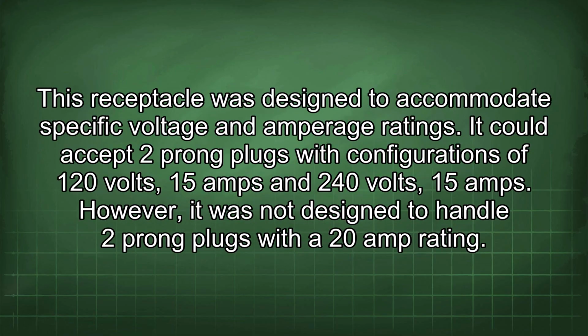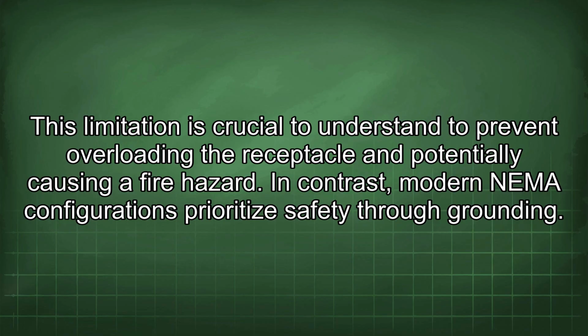This receptacle was designed to accommodate specific voltage and amperage ratings. It could accept two-prong plugs with configurations of 120 volts, 15 amps, and 240 volts, 15 amps. However, it was not designed to handle two-prong plugs with a 20 amp rating. This limitation is crucial to understand to prevent overloading the receptacle and potentially causing a fire hazard.